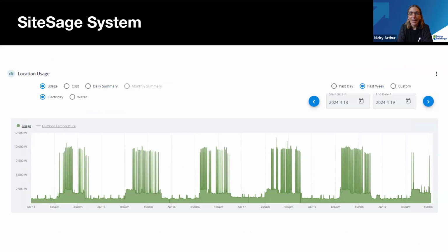In this case, a maintenance alert was triggered due to unusual electrical draw—one of the rooftop units was short cycling. You can see less electricity overnight, typical usage during the day, but then these spikes throughout the day, which is the short cycling of the rooftop unit. An alert was sent to the maintenance team, who were able to go in and have a look. We can pull the trend logs and try to diagnose as much as possible remotely.